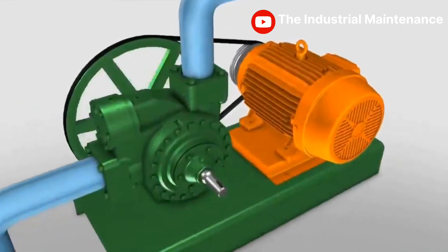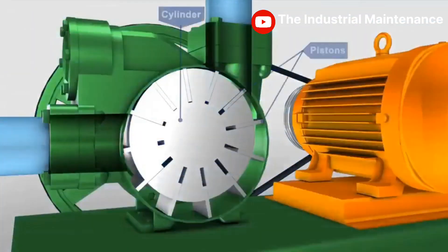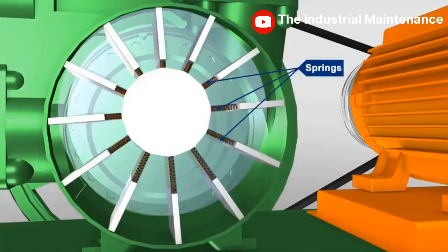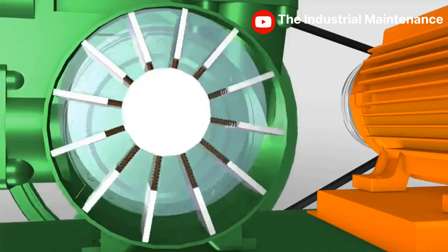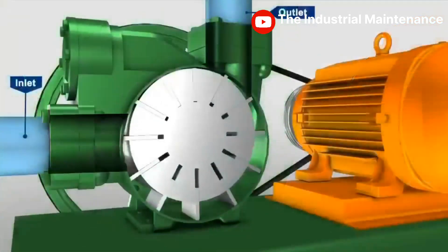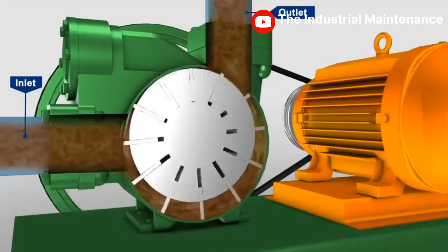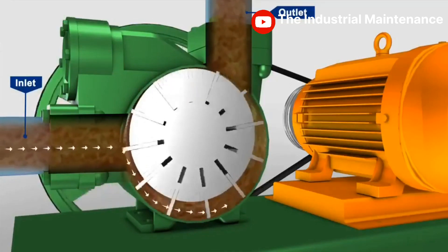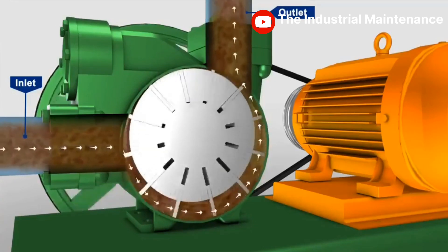The vane pump includes a rotating cylinder containing equally spaced radial pistons arranged radially around the cylinder centerline. A spring pushes the pistons against the inner surface of an encircling stationary ring mounted eccentric to the cylinder. The pistons draw fluid during half a revolution and drive fluid out during the other half. The greater the ring eccentricity, the longer the piston stroke and the more fluid they transfer.